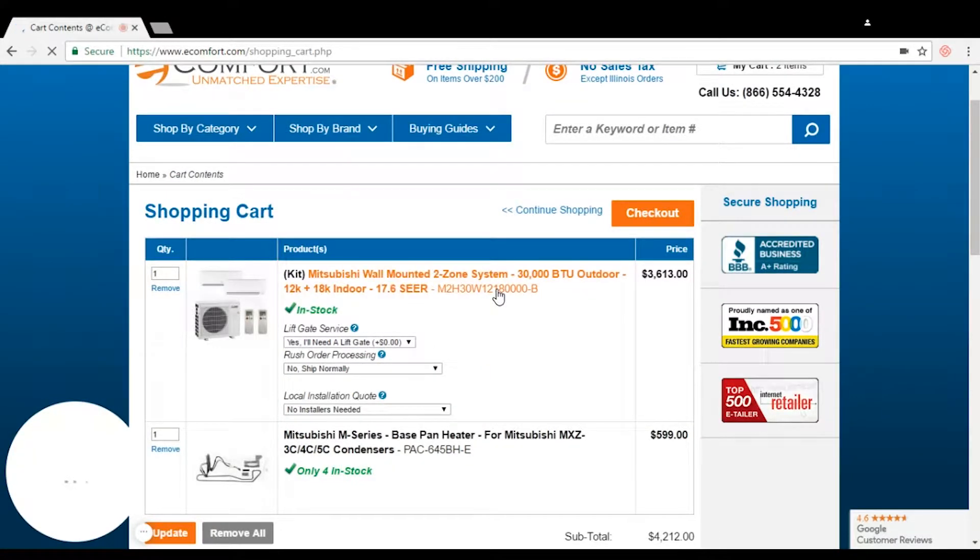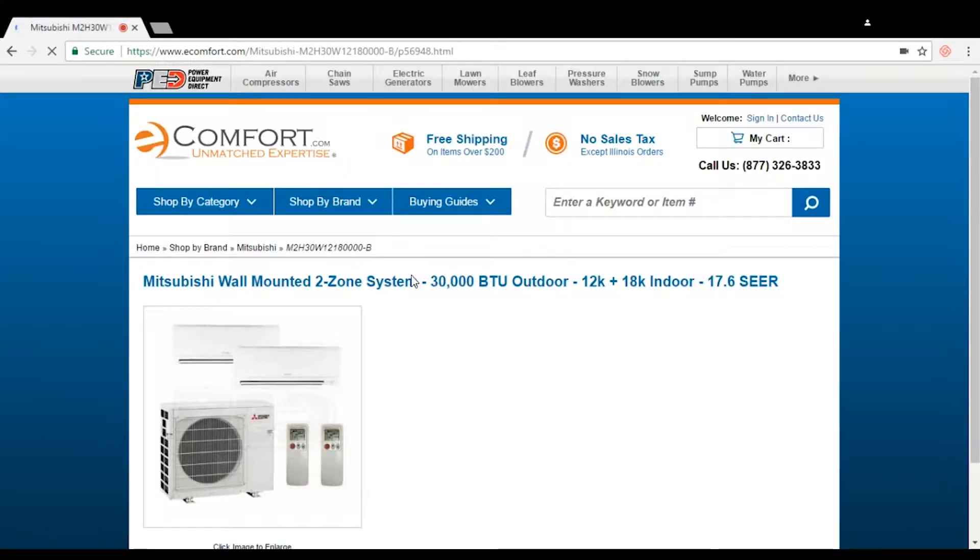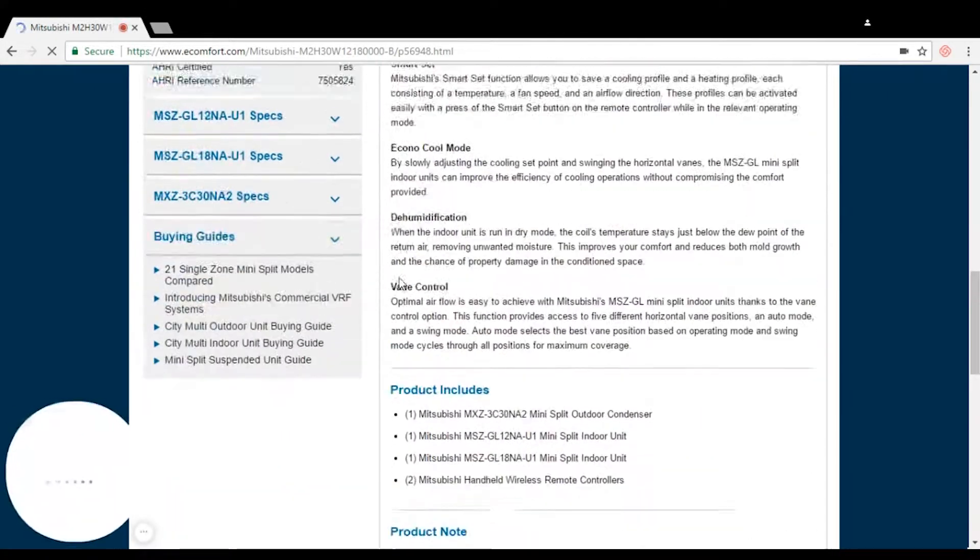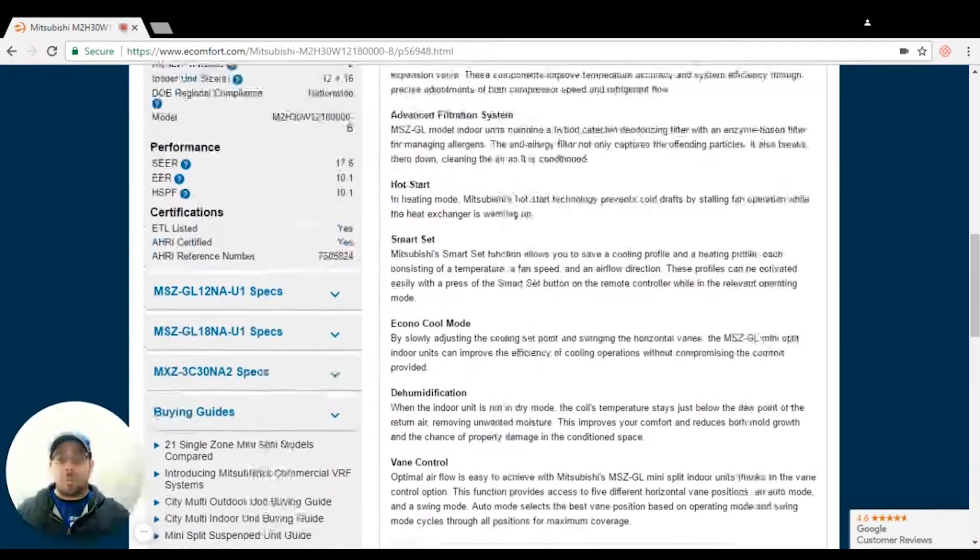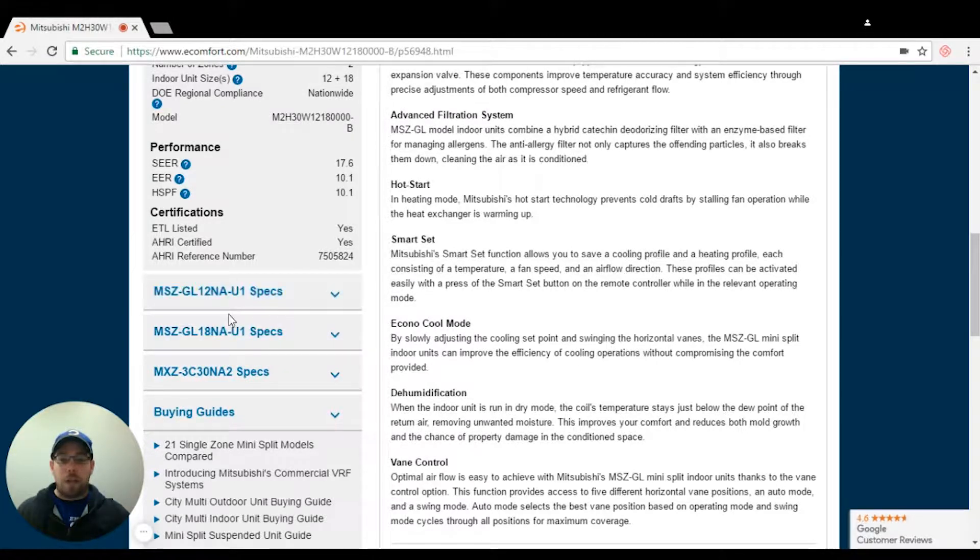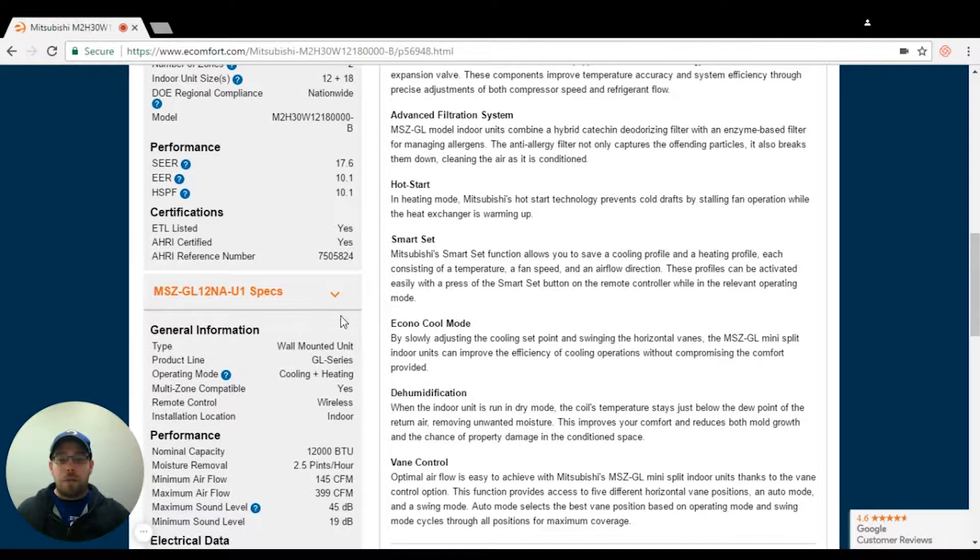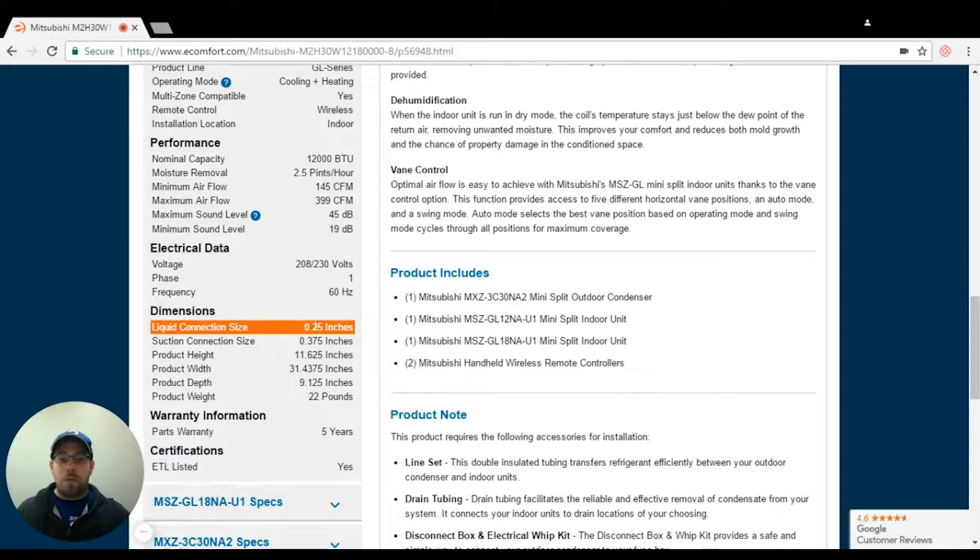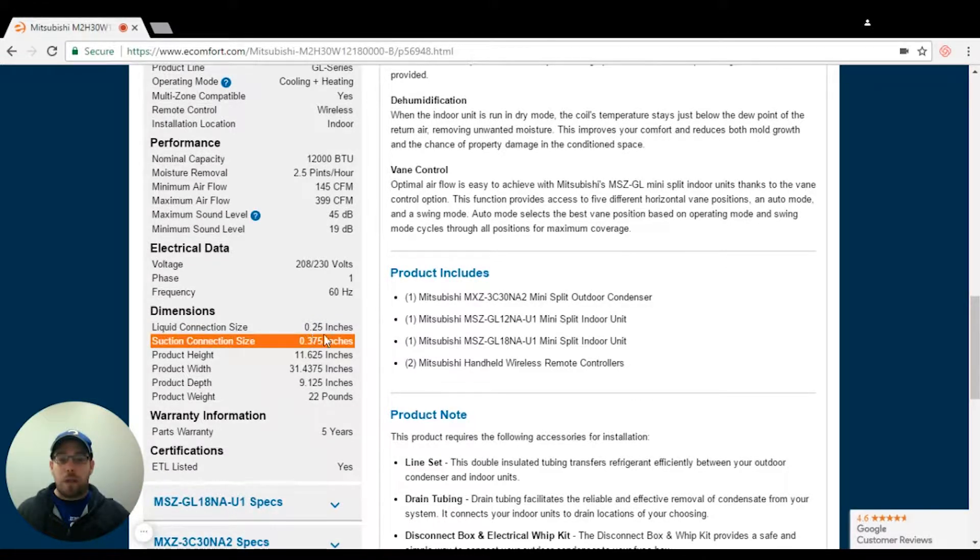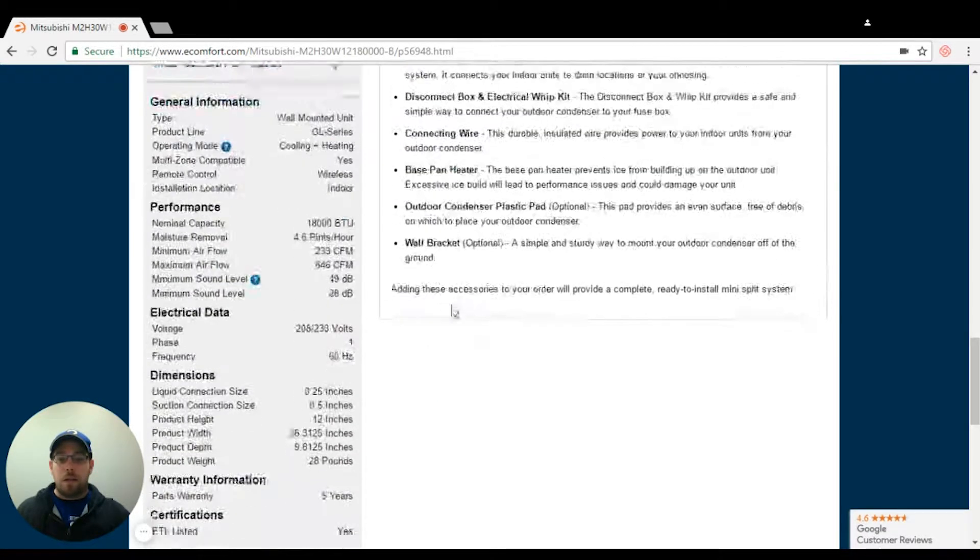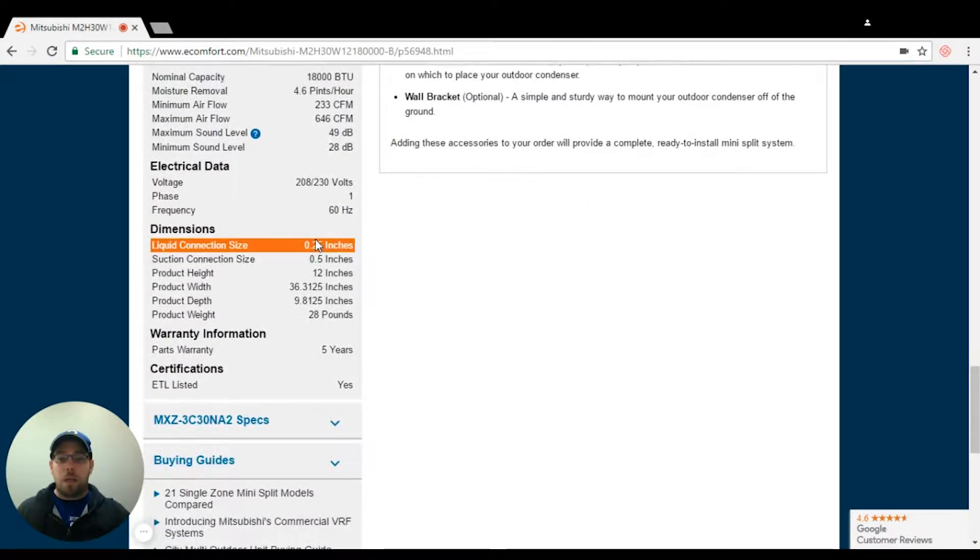Now I'm going back to the line sets. I have a 12 and I have an 18. Now here's the biggest situation. There are two different line set sizes. The 12 is going to be quarter by three eighths and the 18 is going to be quarter by half.